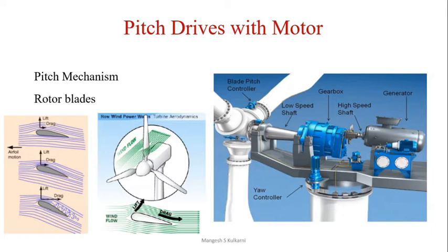The major components of the pitching system are as shown in the figure. The pitch motors are mounted on the pitch drive. The pinion of the drive turns the slew ring and in turn pitches the blades. There are 15 teeth in the pitch drive. The pitch drive rotates the slew ring with low speed and high torque. The pitch motor gives torque for turning or pitching the blades.